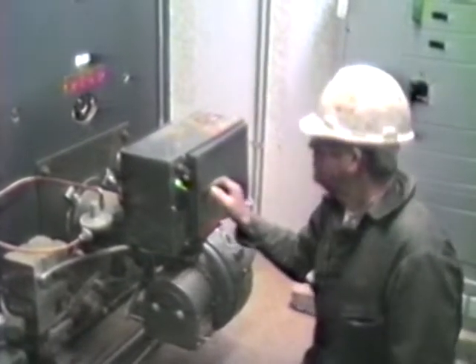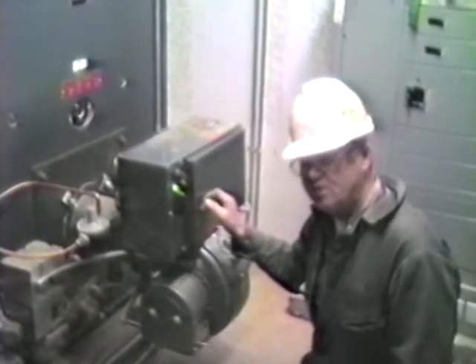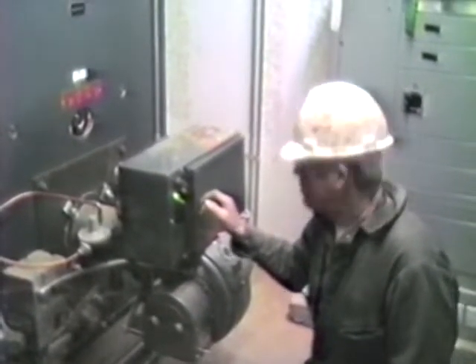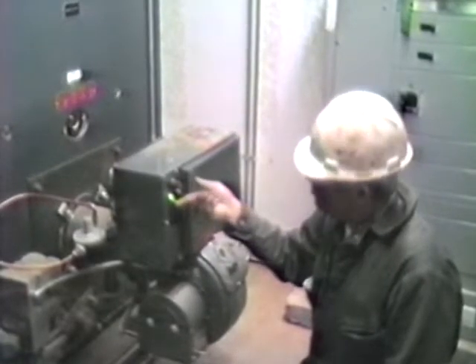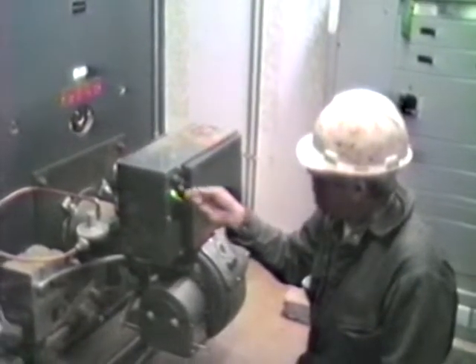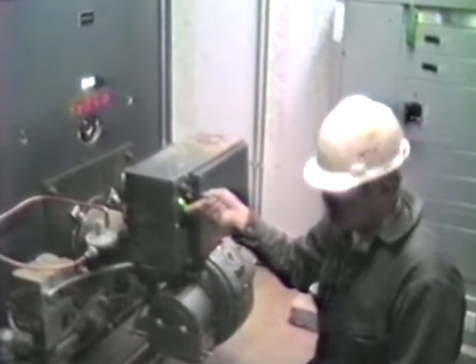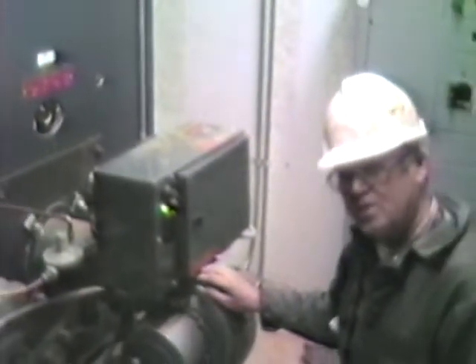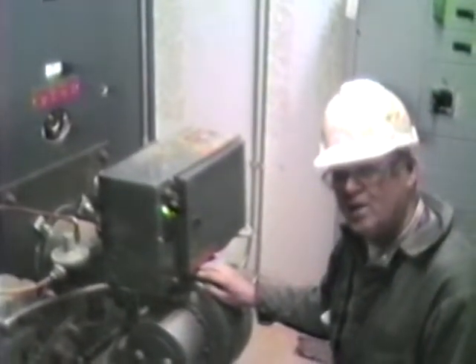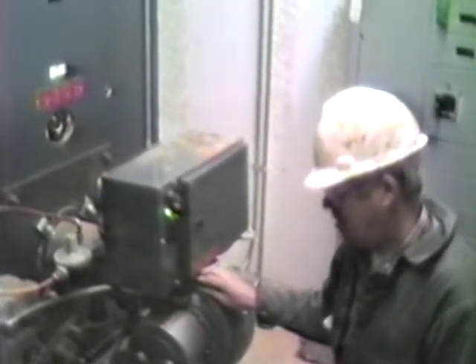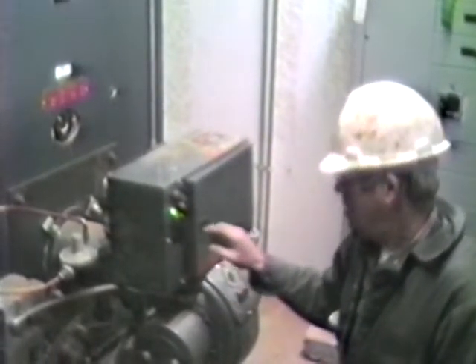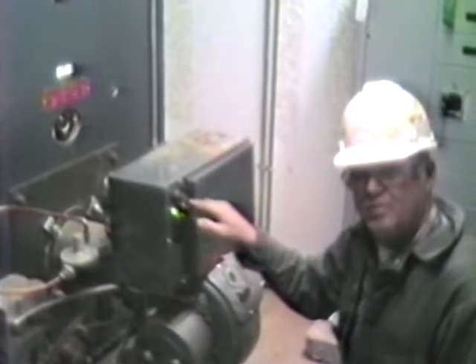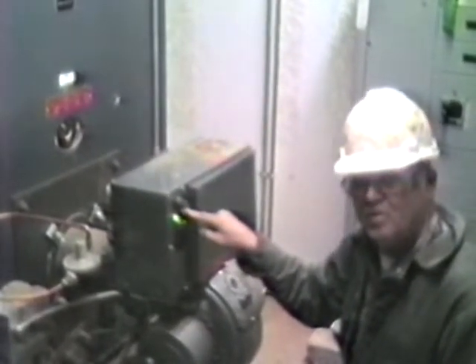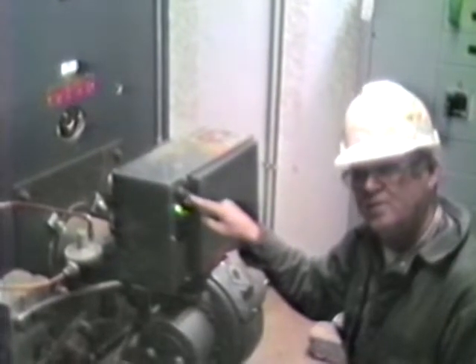Okay, on the control panel, same as chillers, you have two switches. You enable, then it'll show you have power over here. Then you switch this on, this enables the blower to come on first. It will run for approximately a minute and a half. Then the pilot will come on, and immediately this light right here will come on to show that the main burner is ignited.